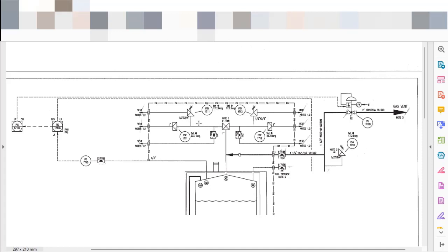This branch here will have the same pressure as the vapor phase of the vessel. So I need to change the position of the diverter valve to the other side, and to be able to remove the safety valve or the rupture disc, I need to open the vent valve and depressurize this branch. With that I have safe conditions for the operator, the maintenance personnel, to remove this. And once everything is okay, I add the devices again to their location, and I close the vent valve.